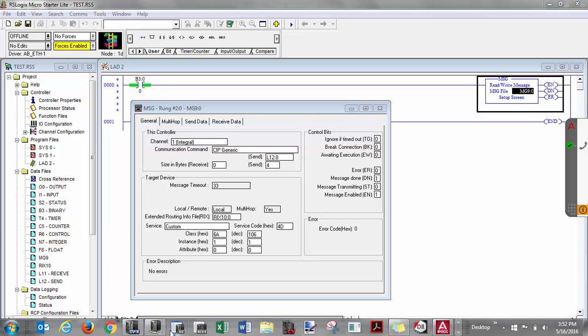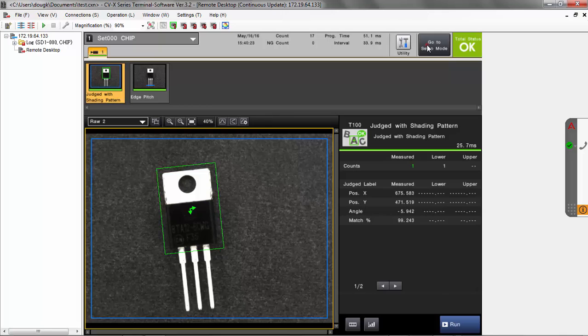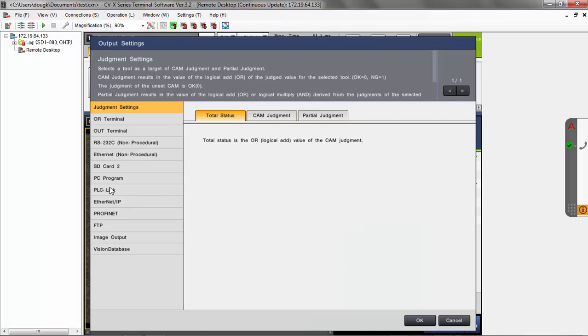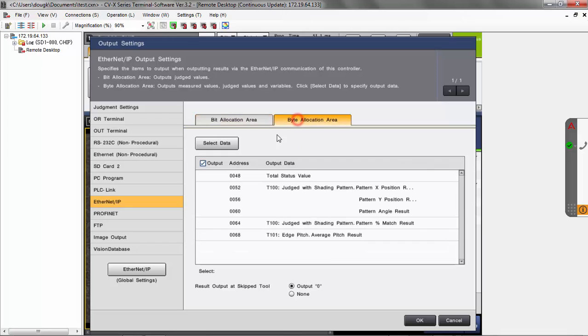Going back to the CVX side, we are setting it up to output several items over EtherNet/IP. This service will read out the byte allocation area. You can see we've got the total status, X, Y, angle, match percentage, and then an edge pitch — so we have 6 items that we're going to be outputting. That means we're going to need to receive 6 times 4 bytes, which is 24 bytes.